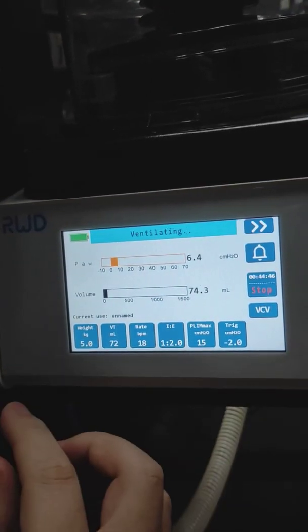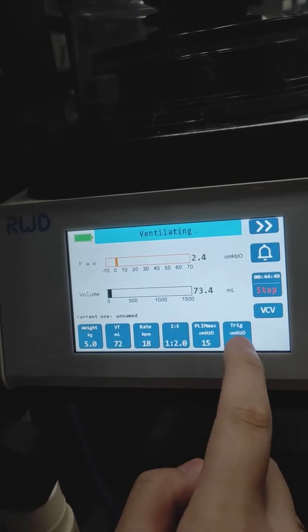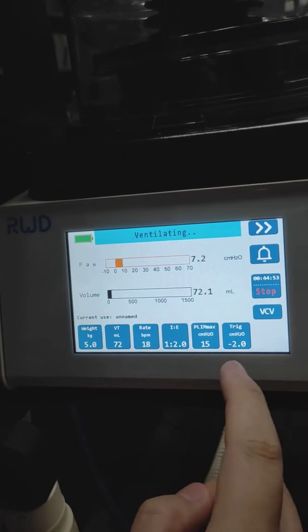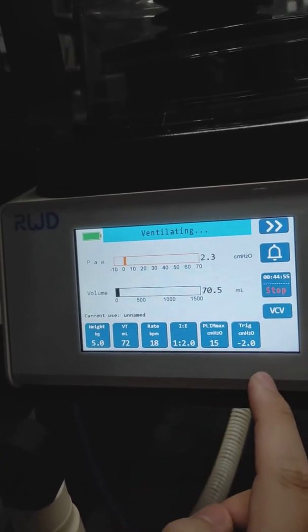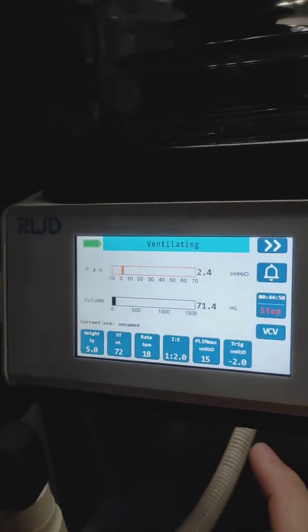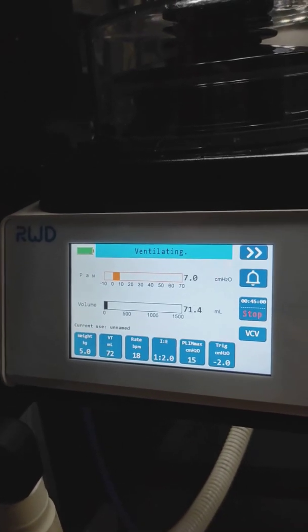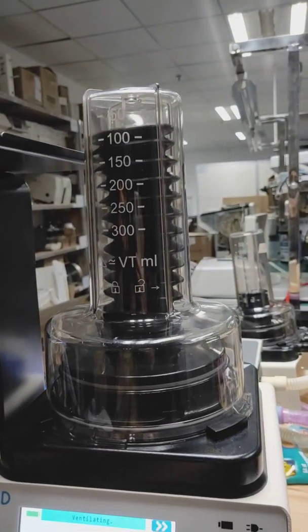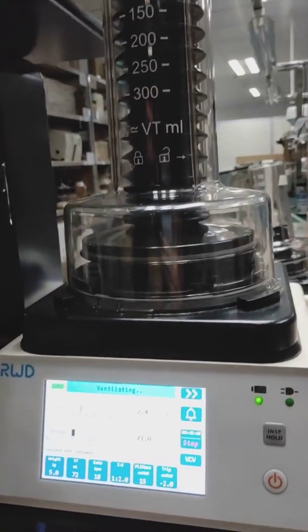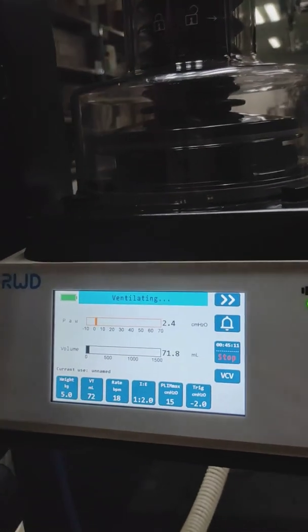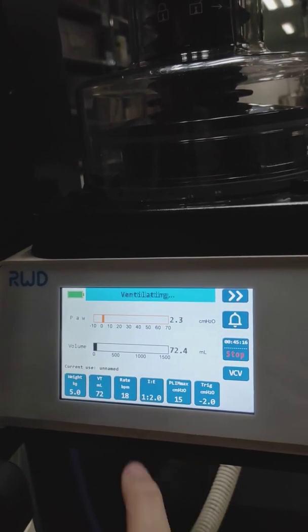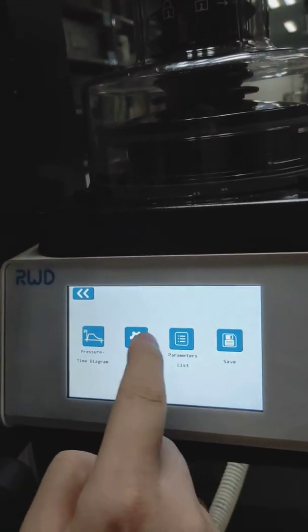And in this mode, we have a trigger pressure, which means that if the machine detects negative pressure, the animal has its own breathing and is going to inhale, so this bellow will immediately follow the animal's breathing and push the air. By doing this, we can avoid the resistance between the animal's breathing and the mechanical ventilation. This works in all three modes.